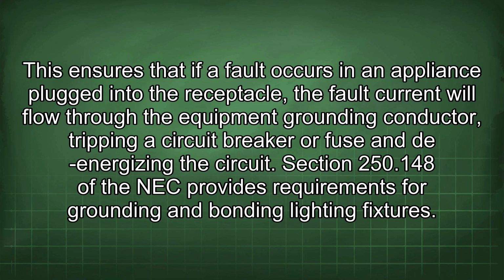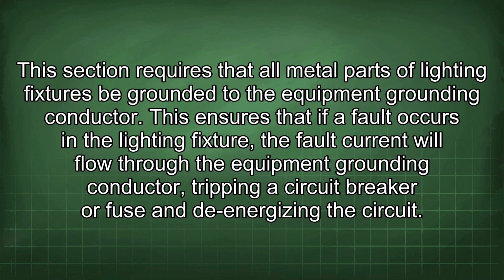Section 250.148 of the NEC provides requirements for grounding and bonding lighting fixtures. This section requires that all metal parts of lighting fixtures be grounded to the equipment grounding conductor. This ensures that if a fault occurs in the lighting fixture, a fault current will flow through the equipment grounding conductor, tripping a circuit breaker or fuse and de-energizing the circuit.